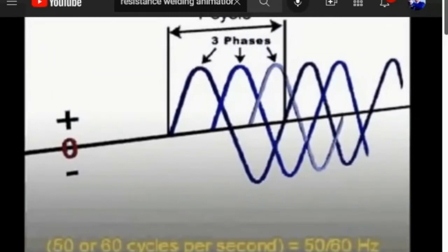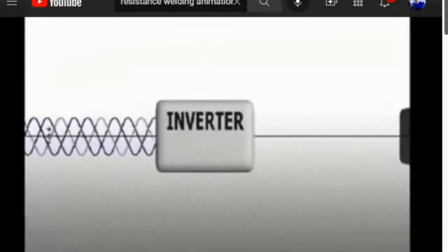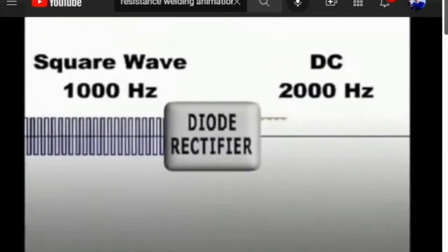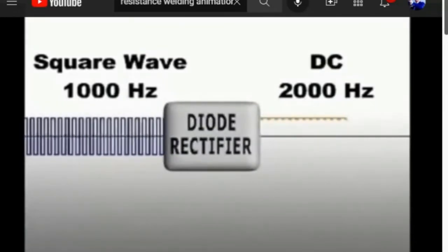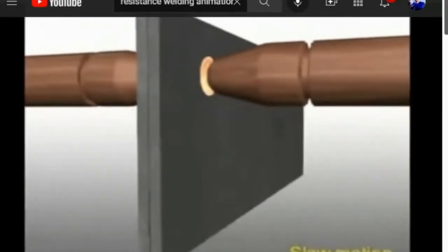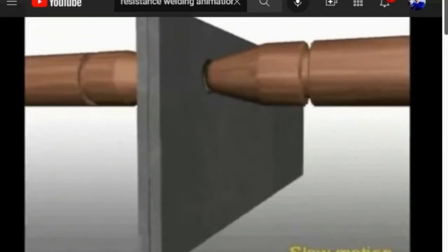The latest welder technology to optimize electricity delivery is to use an inverter. The inverter works exceptionally well with resistance spot welding. The same three-phase current is employed but before converting it to DC power, it is run through an inverter which converts the wave shape into a square wave. Square waves can be controlled better than sine waves, allowing higher operating frequencies. For example, a three-phase DC spot welder using older technology delivers 180 cycles per second, while inverter technology can operate at 2,000 cycles per second. Another advantage is that the current drawn from the voltage source is reduced, providing a surplus of power to other equipment.